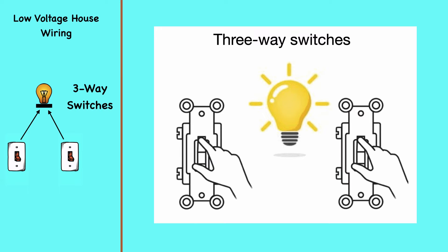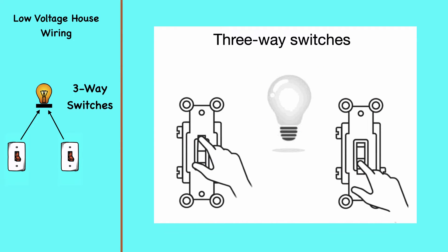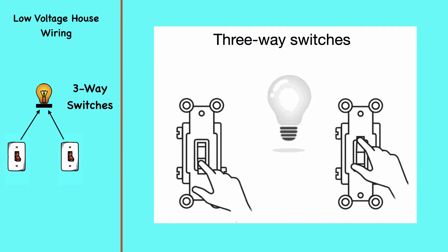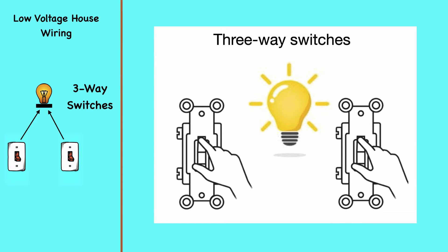Three-way switches have three terminals to carry circuit electricity, and one terminal for a ground wire. Of the three circuit terminals, one is called the common, and the other two are known as travelers. The common terminal may be labeled and is usually a different color than the traveler terminals.